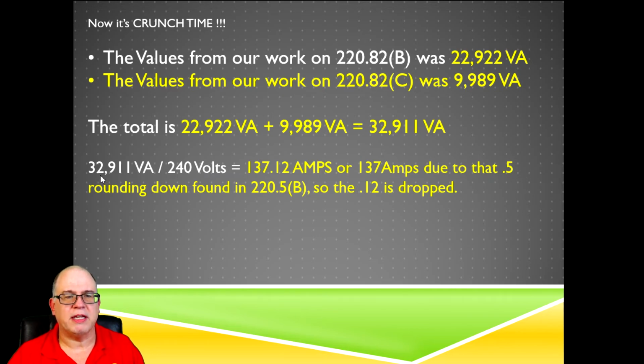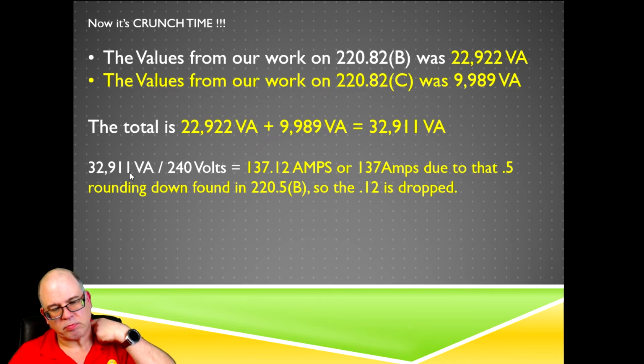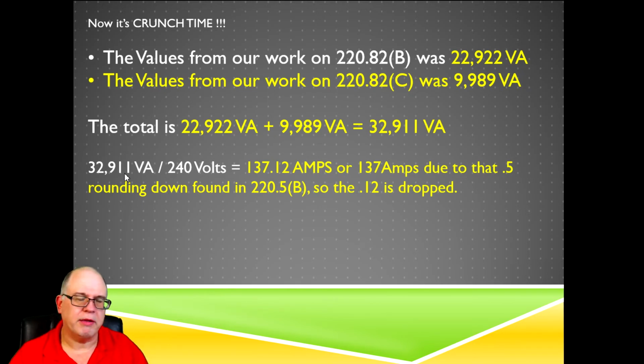Okay, so we're looking here at 32,911 VA, which is kind of our watts, if you will. That's how we get Watt's law and things like that. And so we divide that by 240, and that's going to be 137.12.